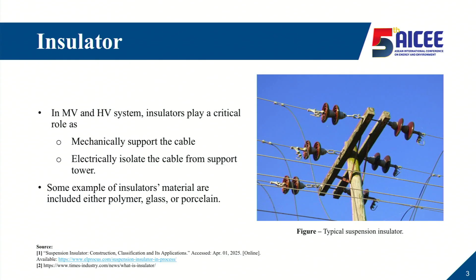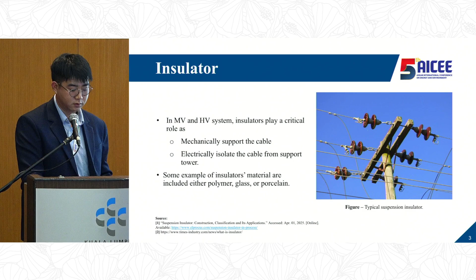In medium and high voltage systems, the insulator plays a critical role to mechanically support the live cable and isolate it from the pole, avoiding electrical shock to people below. The insulator material can be porcelain, glass, or polymer. The insulator is normally divided into 3 parts: the pin, which supports the voltage cable; the cap, which connects to the pole; and the shell, which presents the surface of the insulator to isolate it electrically and prevent leakage.